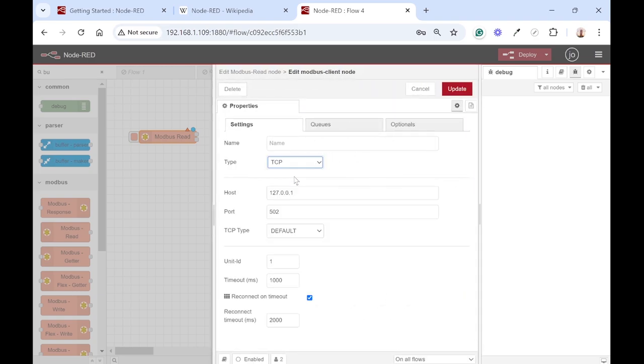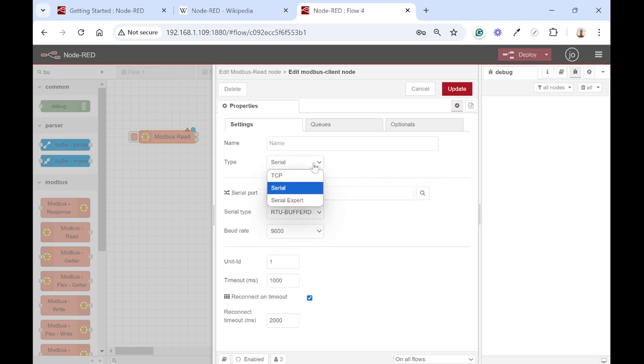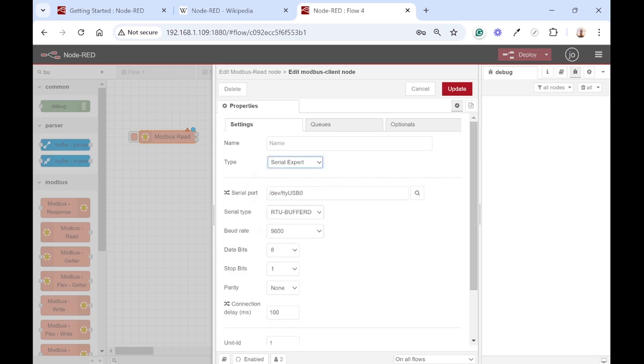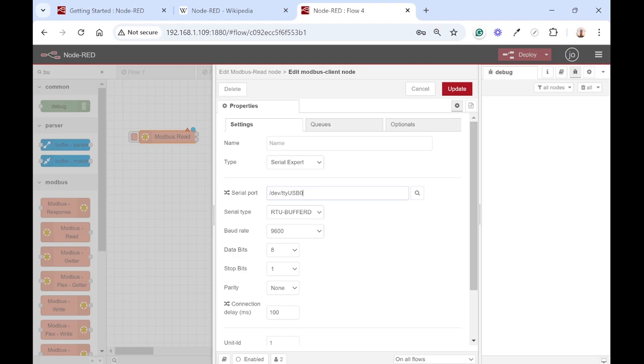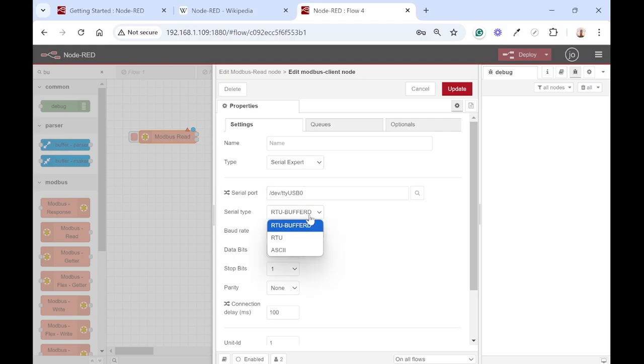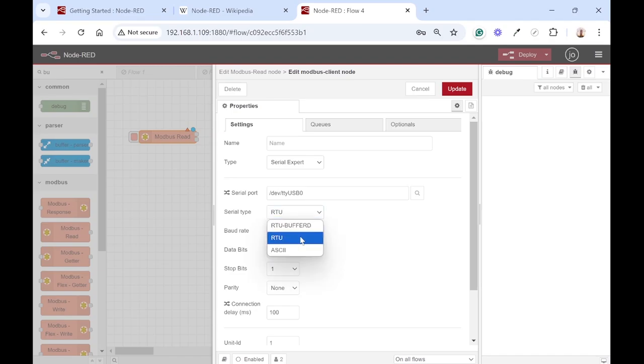You can select TCP/IP if it's Modbus over TCP/IP, or serial, or serial expert, and that expert just adds a few more settings. If you click on that search button it should automatically bring up your serial port. Once we've selected our serial port you must select the serial type, either RTU Buffered or RTU will work, not ASCII. And then the default parameters to connect through Modbus.